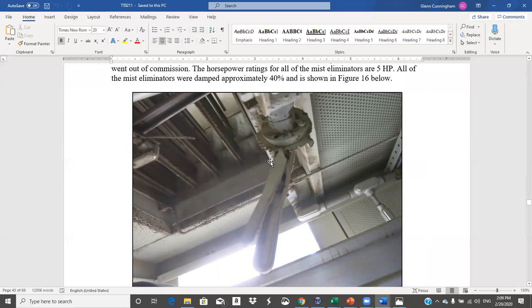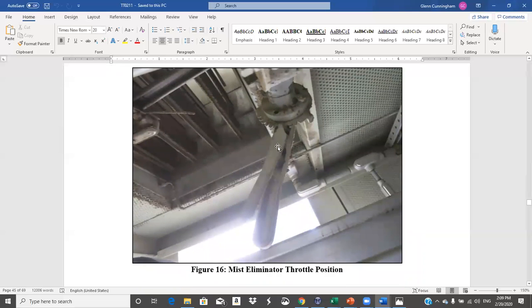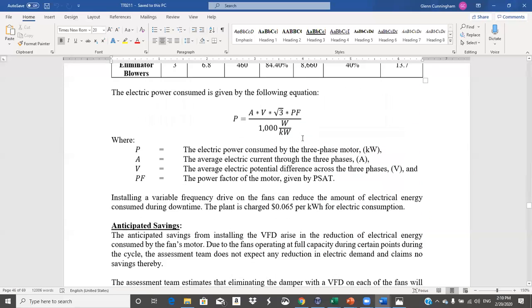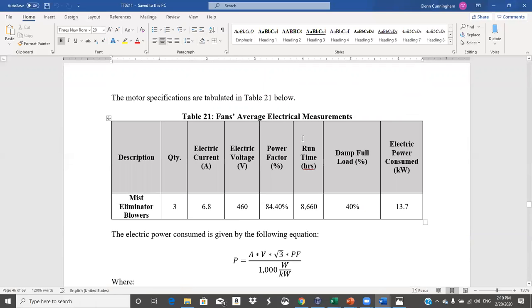And this is a throttling valve, a butterfly valve, and it's throttling. So they were adjusting the flow with throttling, and that's a very inefficient way to do it. I think if this handle moves all the way down to here, that's closed, and if it moved all the way up to here, one way it's closed, one way it's open. It was approximately damped to, it says damp 40%, so it's 60% open, shown in that figure. And so you can put a VFD on that and open that thing up and get the same flow at reduced cost. So they were small, but anyway, that's what that is referring to.